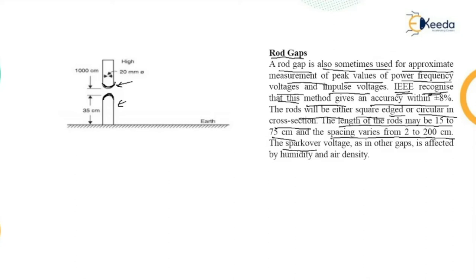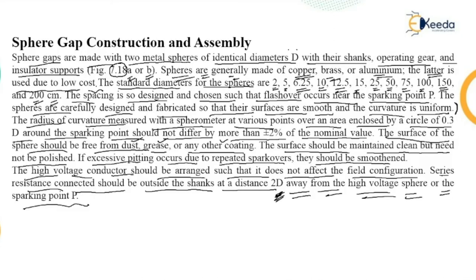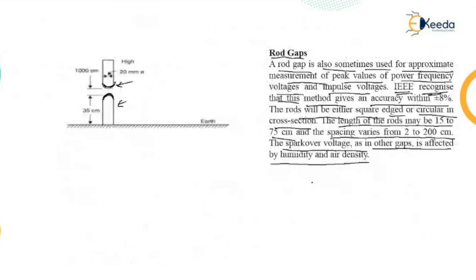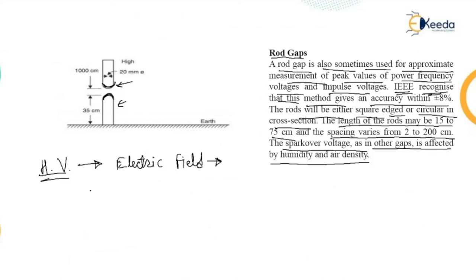The rods may be either square-edged or circular in cross-section. The length of the rods may be 15 to 75 centimeters and the spacing varies up to 200 centimeters. The spark over voltage, as in other gaps, is affected by humidity and air density.